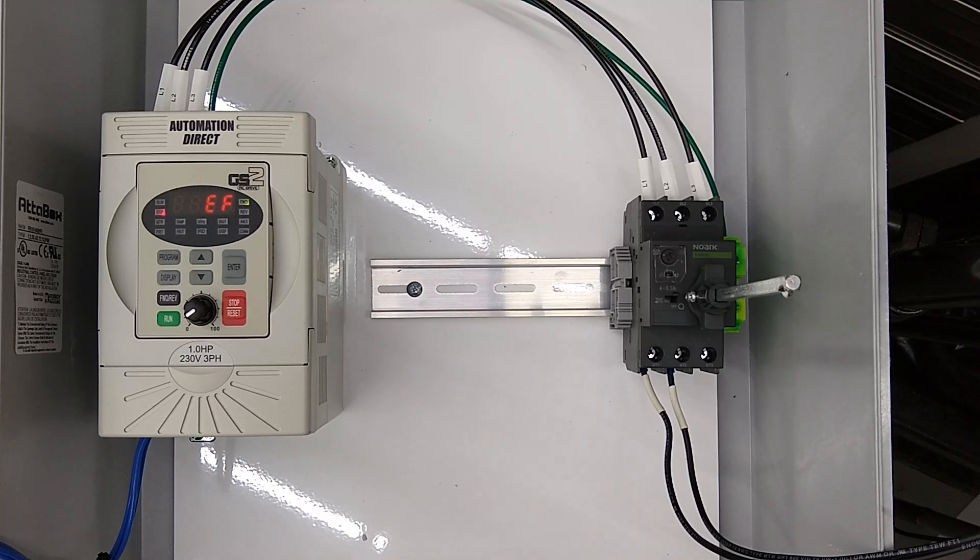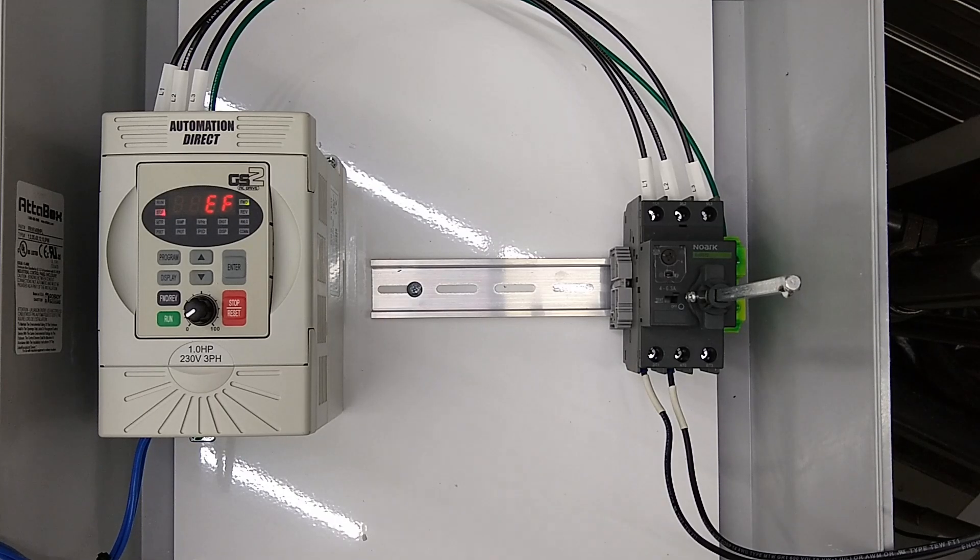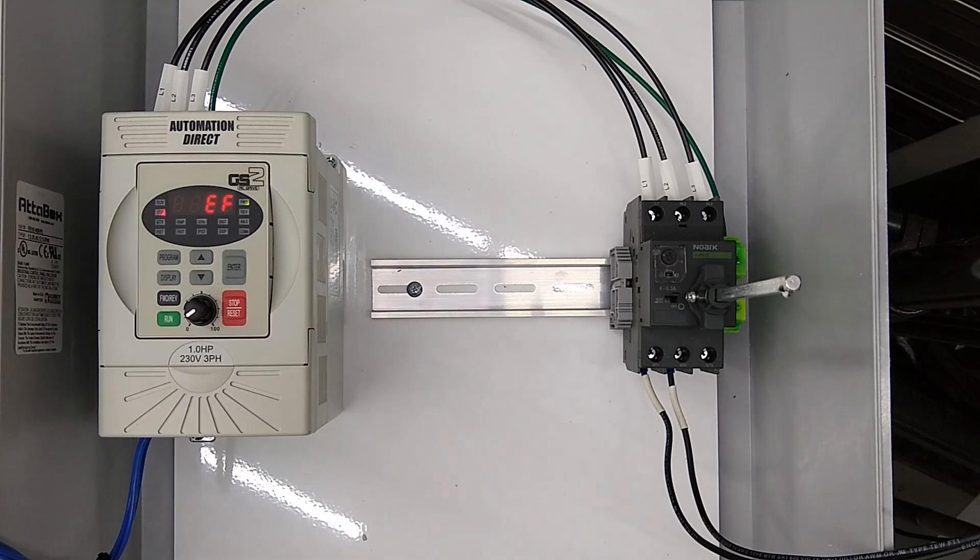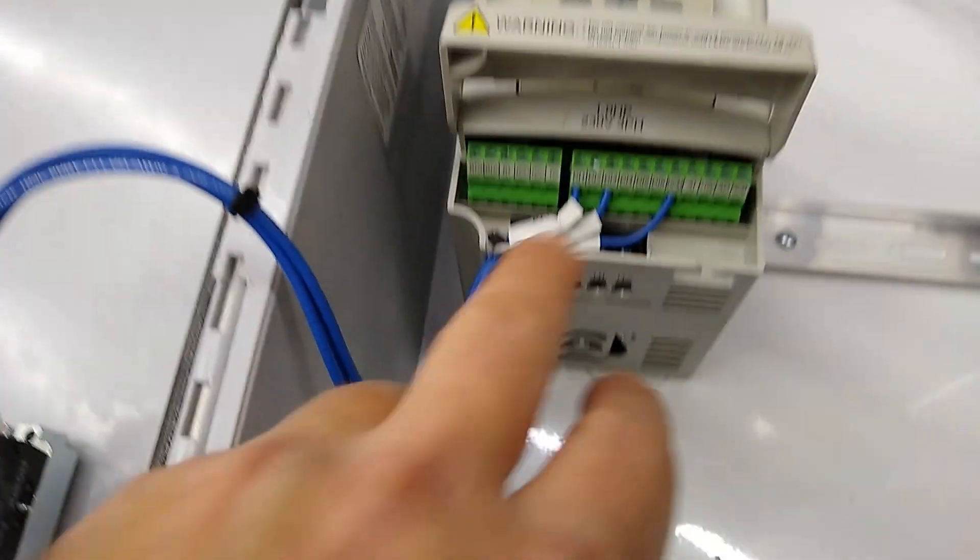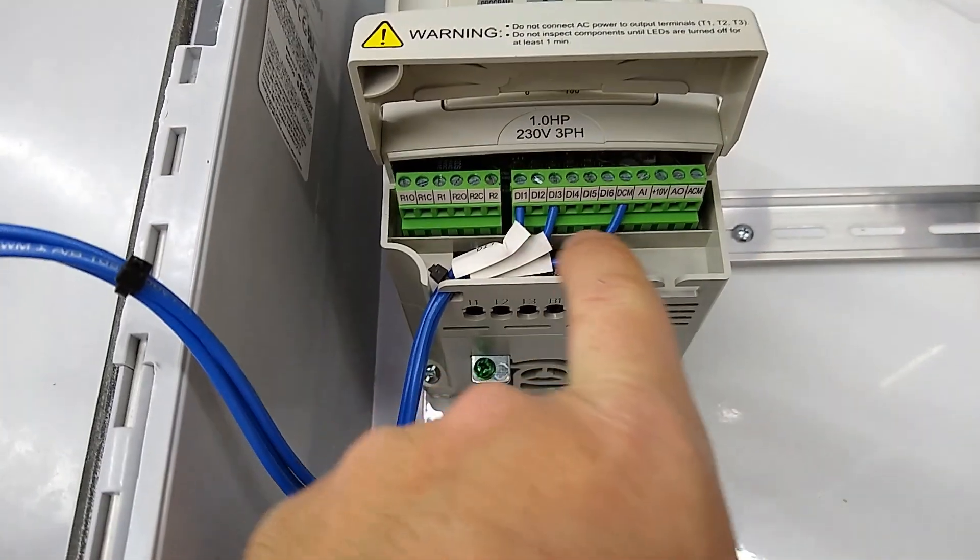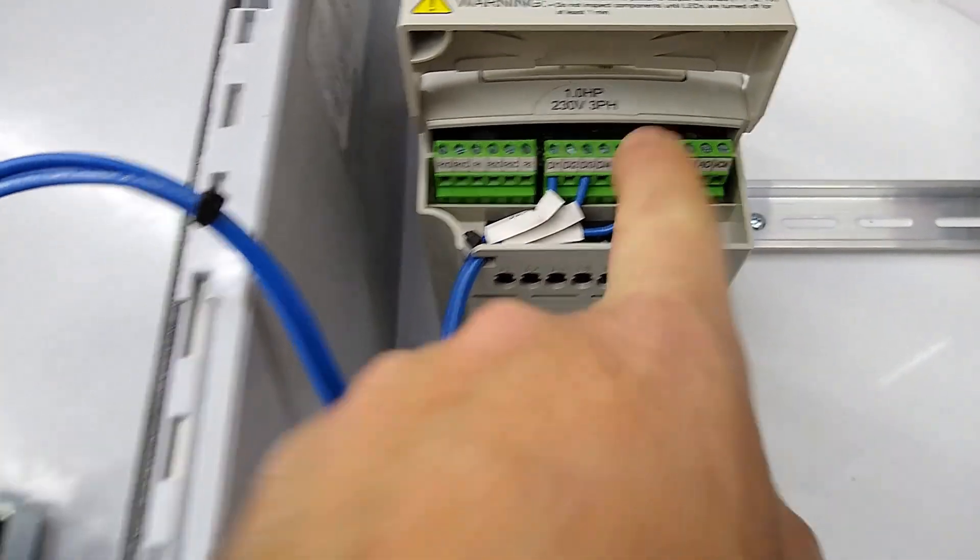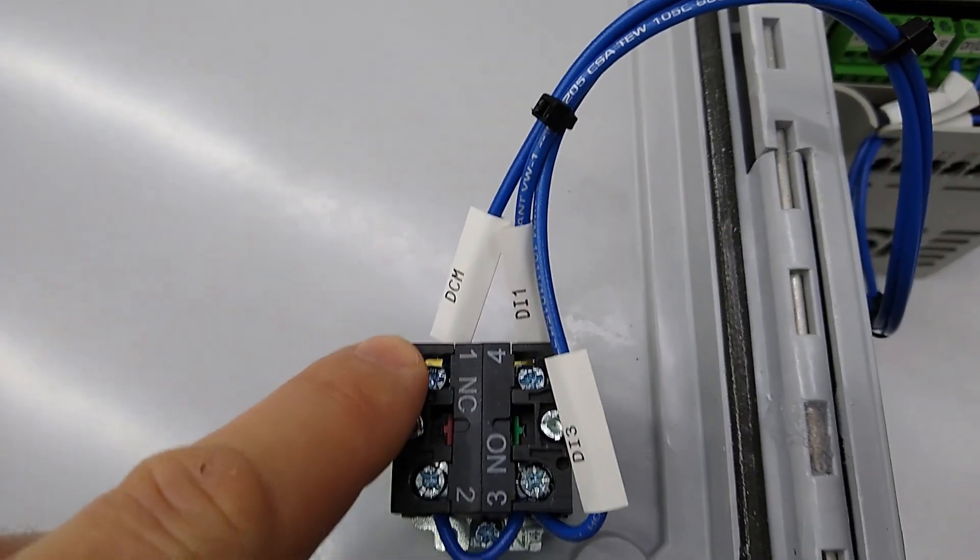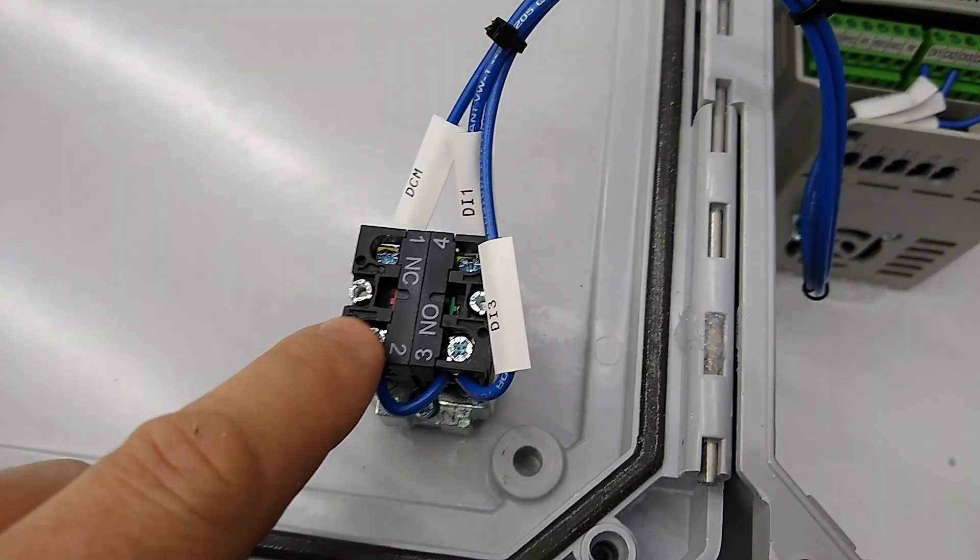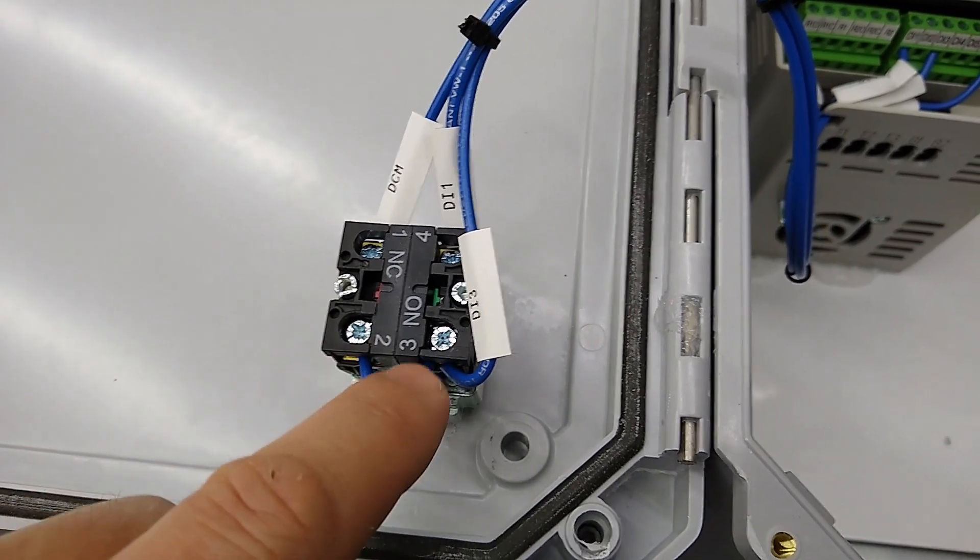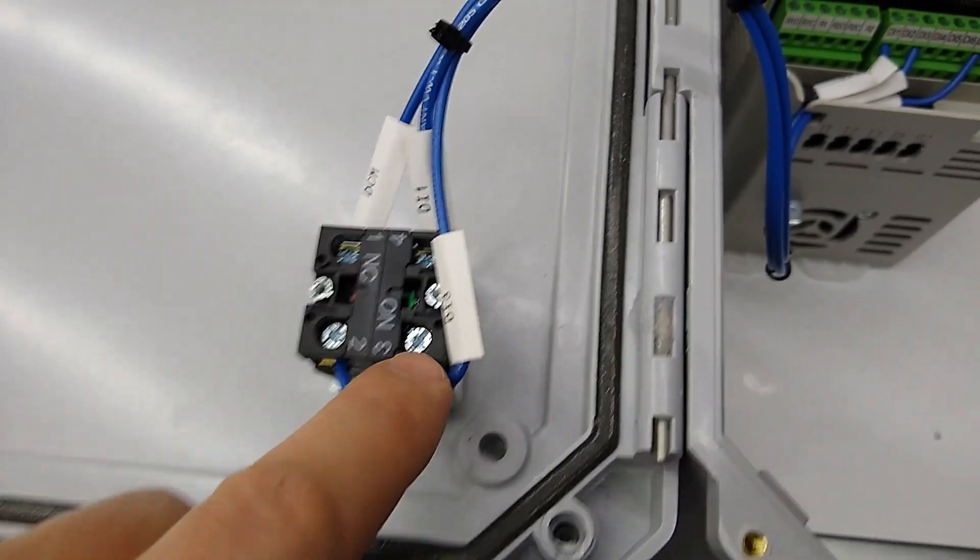Today we're going to go through how to configure an Automation Direct GS2 drive for a start-stop application. We're using the wiring diagram on page 4-23 of the user manual. We have a wire going from our DCM terminal up to one side of our stop terminal, and then we'll have a jumper from the other side of our stop terminal to our start terminal.